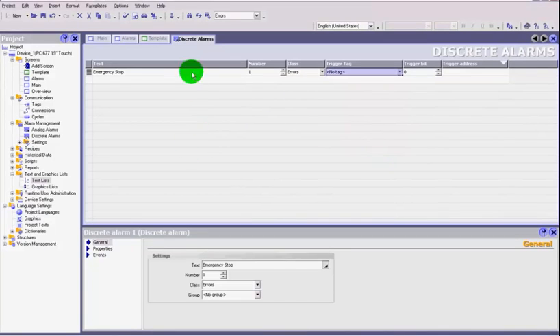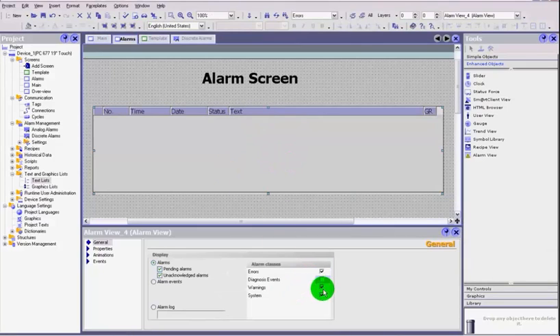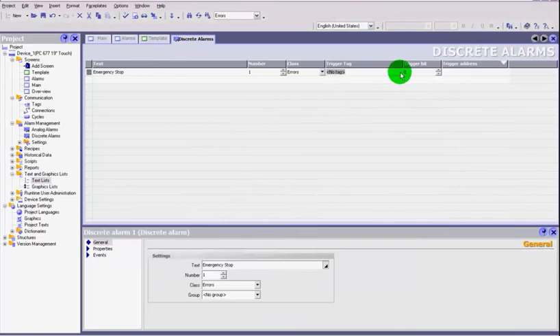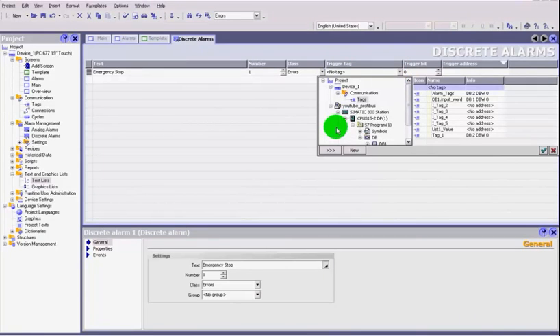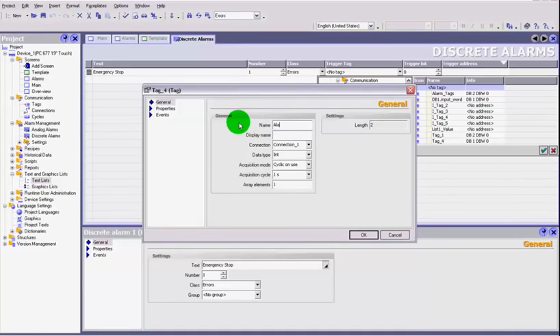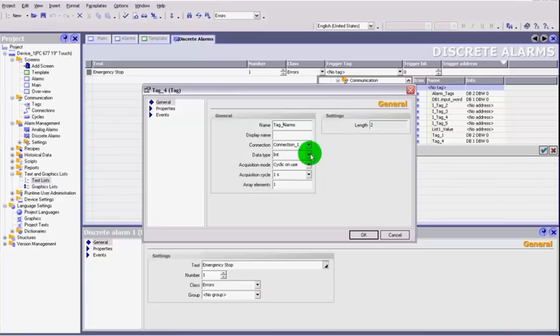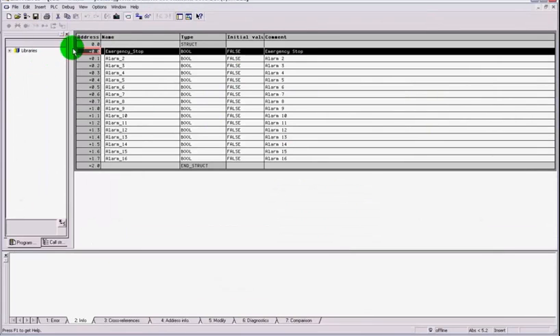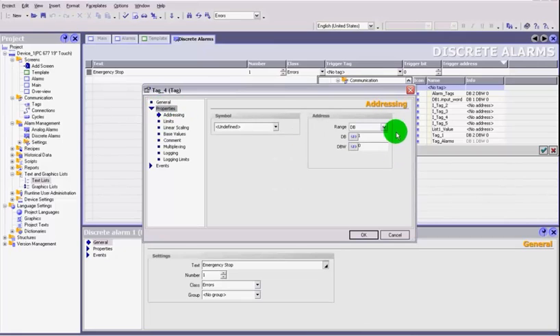We'll leave it as an error. Remember, when we set up the alarm view object, we configured it to display errors. Now for the trigger tag — I've already created one but I'll do it again to show you. Click new, and we'll call it 'tag alarms'. We've connected it to our PLC, which is connection one. We need it to be a word because that's what we have in the DB, even though we've set them up as bits — we have a full word's worth of bits.